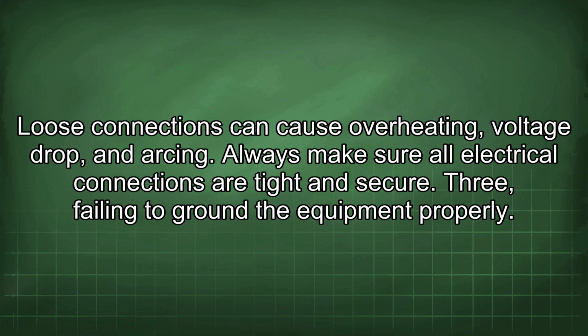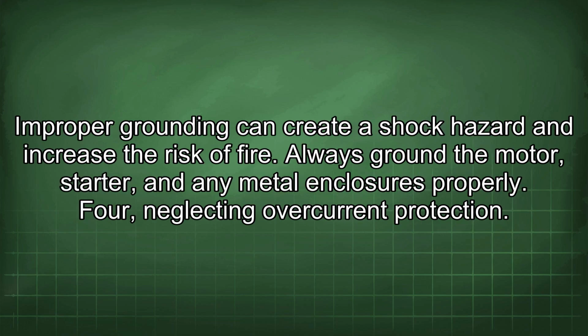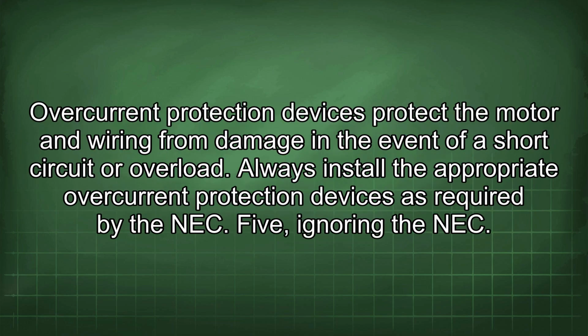3. Failing to ground the equipment properly. Improper grounding can create a shock hazard and increase the risk of fire. Always ground the motor, starter, and any metal enclosures properly. 4. Neglecting overcurrent protection. Overcurrent protection devices protect the motor and wiring from damage in the event of a short circuit or overload. Always install the appropriate overcurrent protection devices as required by the NEC.